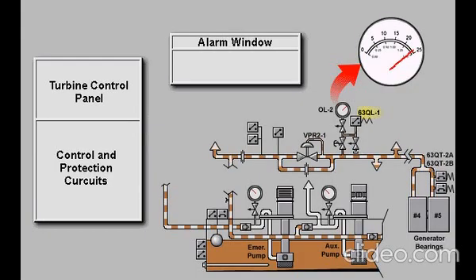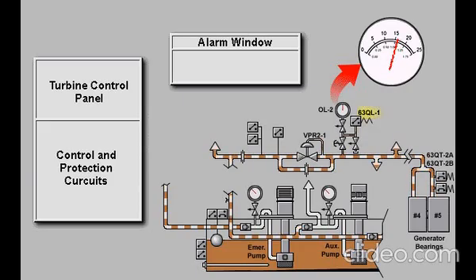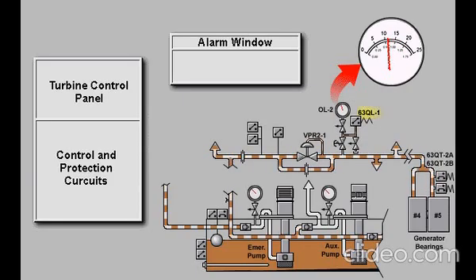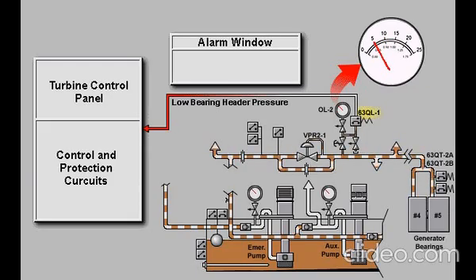Pressure switch 63QL-1 acts as a backup to pressure trip switches 63QT-2A and 2B and will activate the emergency lube oil pump if oil pressure in the bearing header drops below 6 PSI.